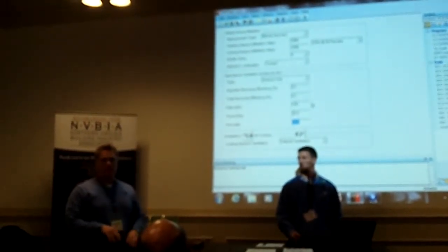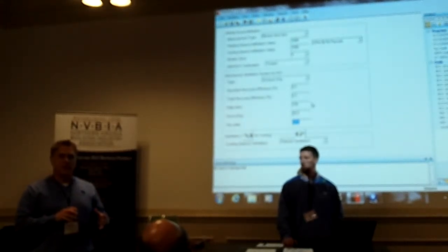Some of the changes in these programs, particularly Energy Star, is that Energy Star 3.0 had a requirement for lot-specific Manual J's—every house had to have its own Manual J done before it could be certified, and we're starting to see code officials ask for those too. That requirement got pushed to January 1st, 2013 by the EPA, but a lot of our clients have been doing them all year anyway.